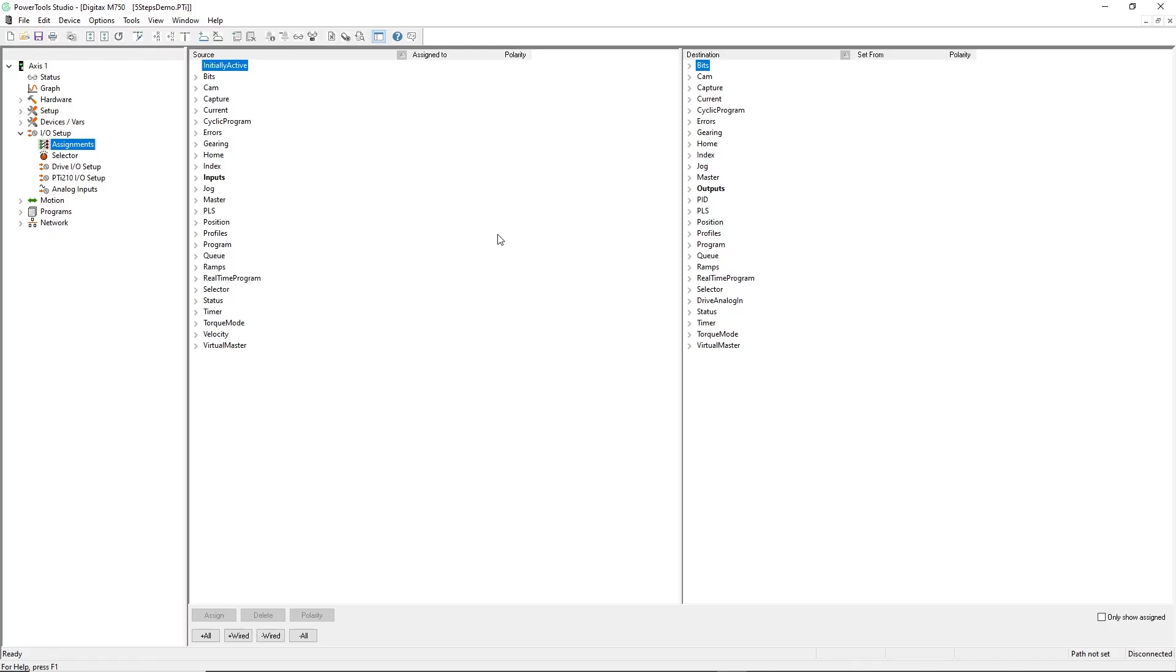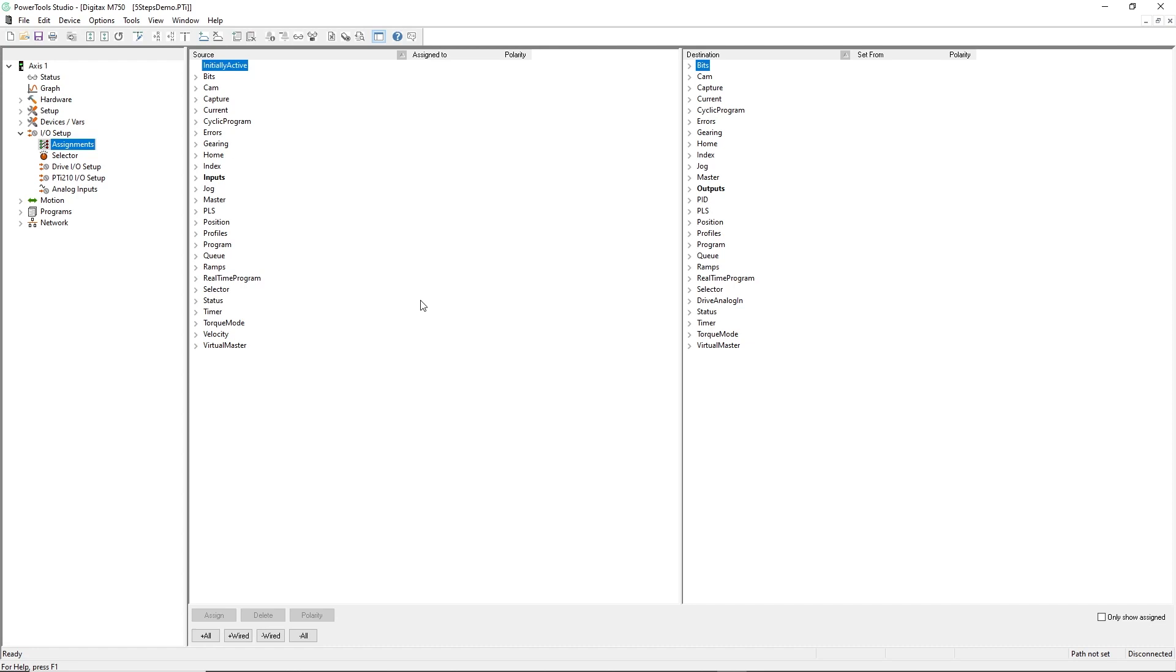One of the more powerful features of PowerTools Studio's software is its ability to map digital I/O to control functions. Here, I have the Assignments view of the Project Explorer open. To demonstrate this feature, I'll begin by assigning my home proximity sensor to digital input number 4 on the Digitax HD M750 drive by dragging the home sensor function and dropping it onto the input like this.